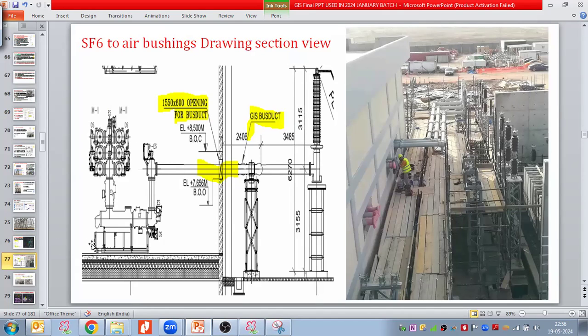So here we have the GIS module placed inside the GIS hall. Here we have the wall of the GIS building. In the wall, we have to make an opening arrangement. This is how we indicate the opening arrangement in the drawing, but this is how it is achieved at the site. This opening we generally take 1.5 meters long, and the wall we generally take as 600 mm wide. In that wall, the duct opening is here, the duct is coming outside, going here, and this duct is connecting to the gas to air bushings. It is at the site, and it is indicated like this in the drawing.